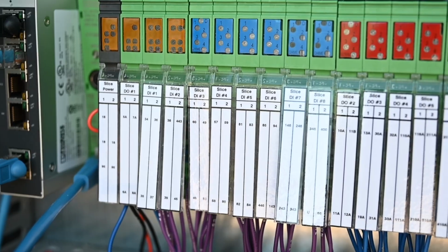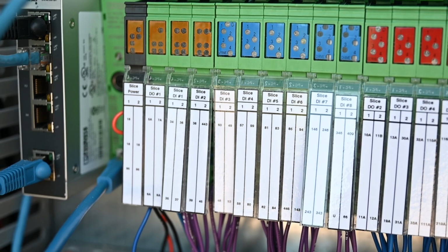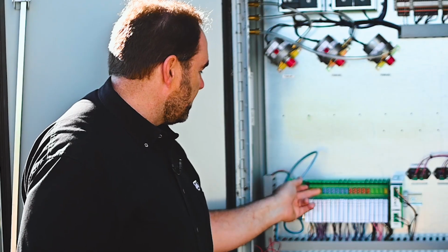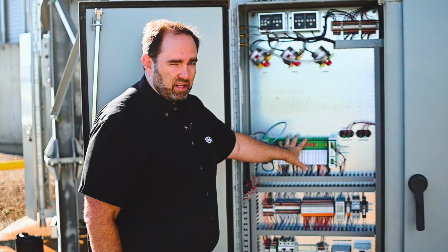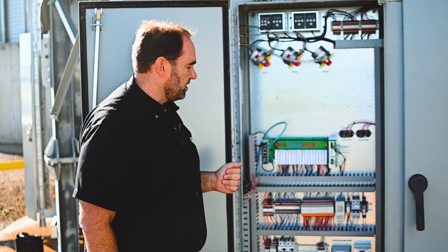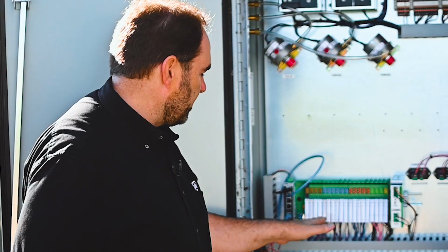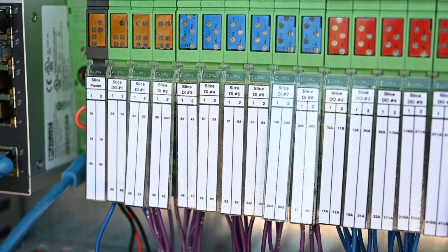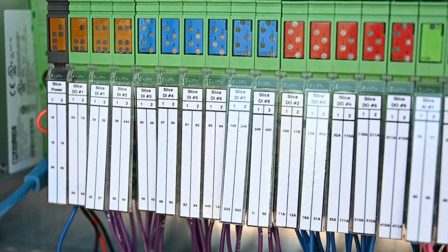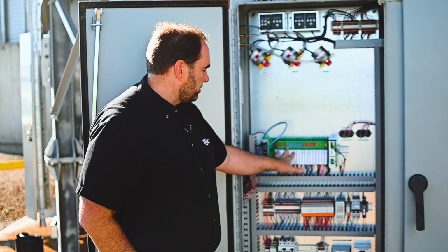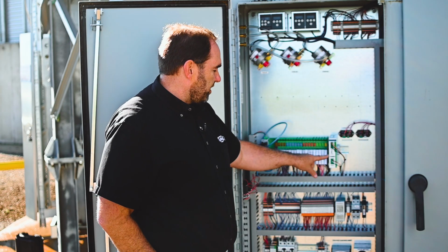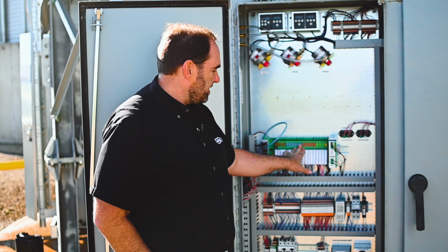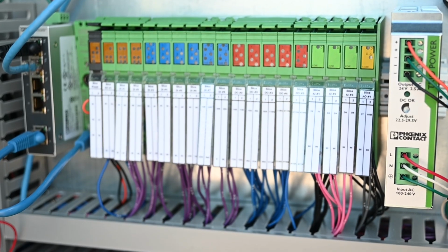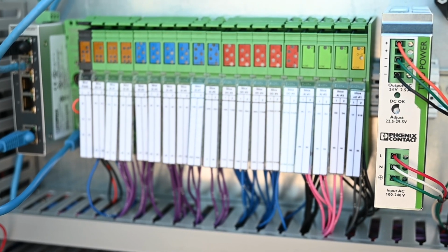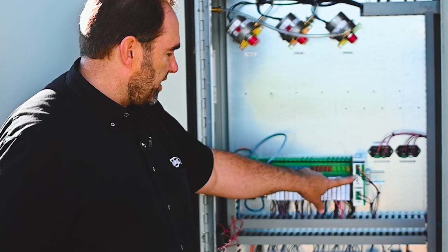Coming down, we have just an Ethernet switch, and it's just a simple Cat 5, Cat 6 Ethernet switch. And then this is a PLC, a programmable logic controller. And the PLC is really the main brain of the dryer. So all the inputs and outputs come into the PLC. The PLC operates on 24 volt DC power. So low voltage safe. This is the power supply that gives power to the PLC and most of the safety circuits on the dryer. So we have 110 volts coming in, 24 volts DC coming out.